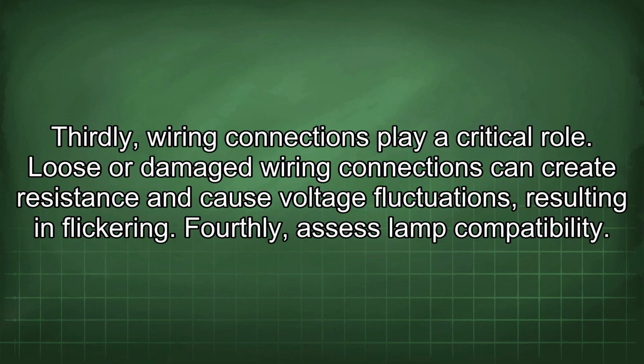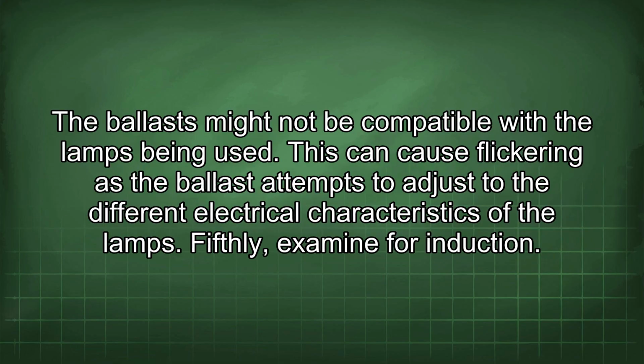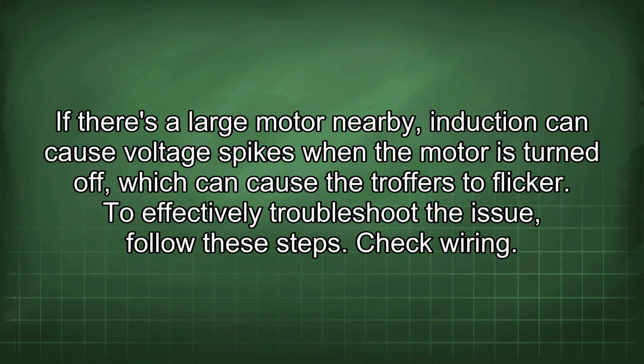Fourthly, assess lamp compatibility. The ballast might not be compatible with the lamps being used. This can cause flickering as the ballast attempts to adjust to the different electrical characteristics of the lamps. Fifthly, examine for induction. If there's a large motor nearby, induction can cause voltage spikes when the motor is turned off, which can cause the Troffers to flicker.